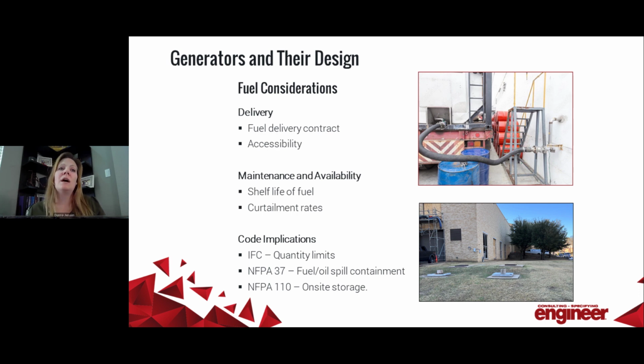and cycling it back in to freshen it up. Another thing to be aware of on the fuel system side is the possible curtailment arrangements that exist between the facility and natural gas companies. Now, remember, we're talking about diesel here, so I'm not talking about natural gas generators. I'm talking about other users in the system. A key example of that would be if you have a hospital that has dual fuel boilers, where it uses natural gas as a primary source, but diesel as backup. If contracts with the utility company are made, which many times are made outside of the engineering design team's knowledge, that could have an impact on your system.